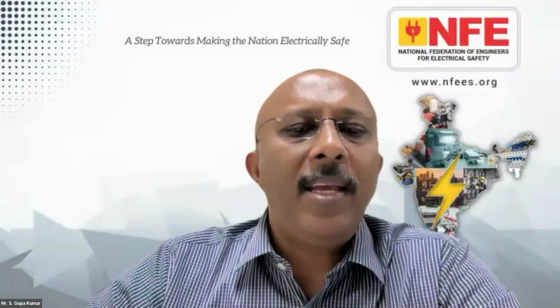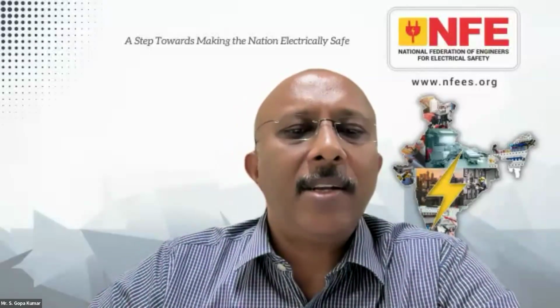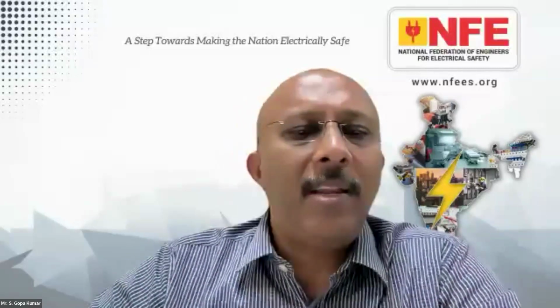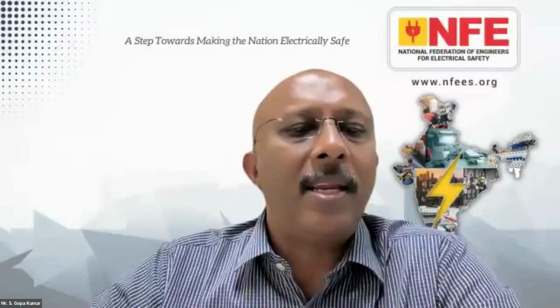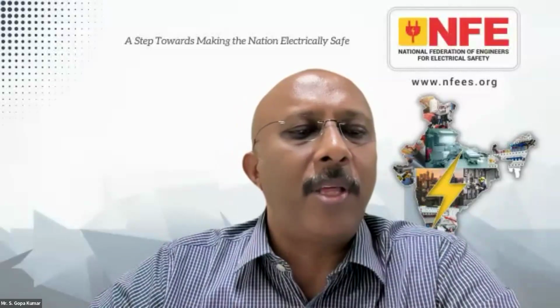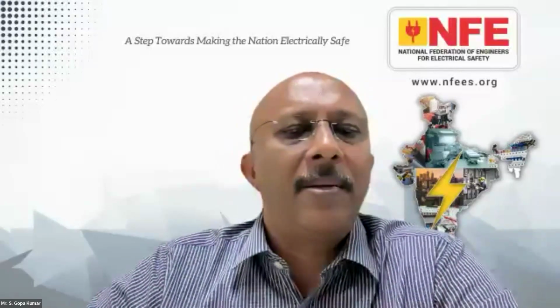Instead of the lift motor, I would say the entire electrical system of the lift, including the VFD. I would not be able to answer it in terms of motor per kilowatt or equipment per kilowatt, but generally, with variable frequency drives in the circuit and depending upon the rating, we have 300 milliamps or 500 milliamps RCDs connected in the circuit.